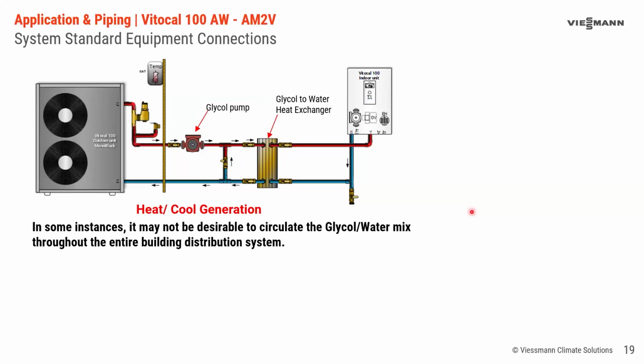So there are a couple of other options we could do here. What if your building isn't suitable for, or the customer doesn't want, glycol throughout the whole building? In the native setup, we're going to put glycol in the system in northern climates, obviously, and we're going to send that to the buffer tank, and then it's going to send it out to the heat emitters or air handlers, or however we're going to do that, and the whole system is now full of glycol. There may be some instances where that's not suitable. It may be a preference of the engineer, it may be a preference of the homeowner, it may be the type of piping you're using, or it may be the pumps that are in the system, because remember, if we put glycol in it, we're going to have a different pressure drop and friction loss, because glycol is more viscous, right? So maybe your building doesn't have pumps that are suitable for glycol when you're replacing the boiler or something like that.